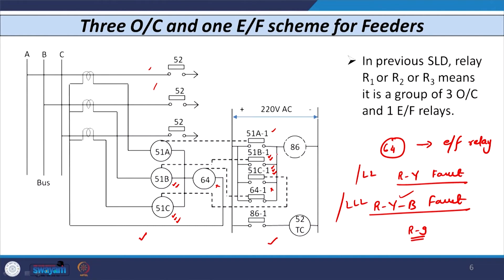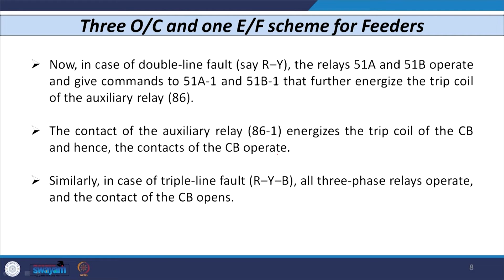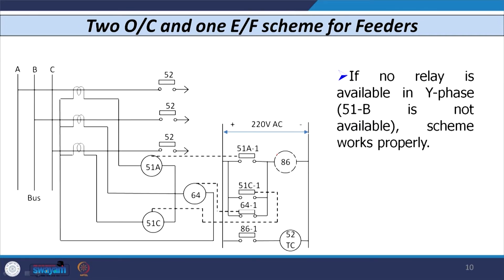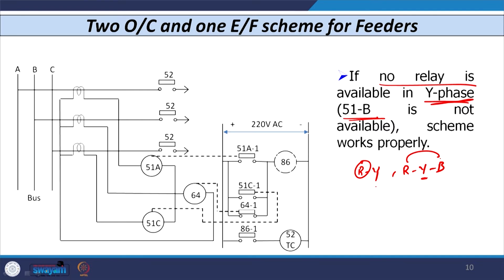Sometimes it may be possible that if one unit is removed from the scheme, it becomes the two overcurrent and one earth fault scheme. If unit 51B has been removed from Y phase, and an R-Y fault occurs, though there is no unit in Y phase, the unit 51A in R phase still operates and further tripping is given. If an R-Y-B fault occurs and there is no unit in Y phase, units 51A and 51C operate and further tripping is initiated.